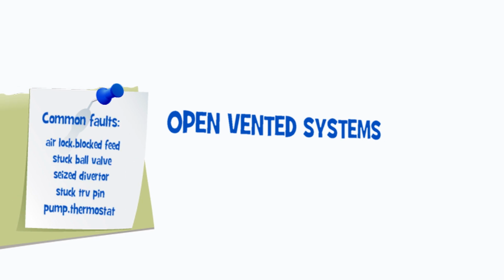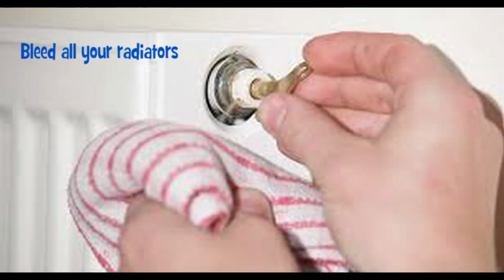Open-vented system common faults. Airlock symptoms. Starting from downstairs working your way up, bleed every radiator as shown in the picture. Any radiators which still do not work, will have to be left open at the bleed valve. Place a receptacle and towel under the radiator, turn your heating on and be patient. Eventually air will be heard leaving the valve and your radiator should start to warm.